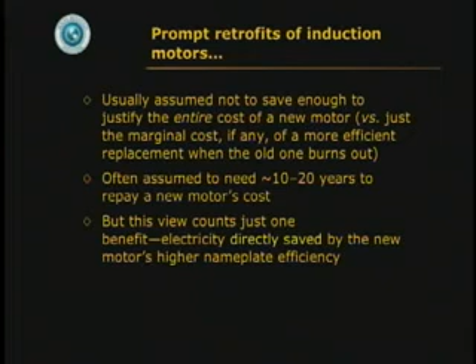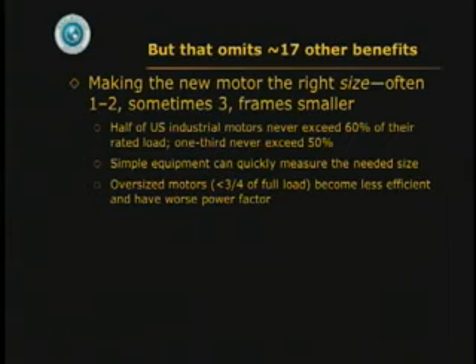It turns out that half of our industrial motors never get above 60% of their rated load. A third of them never exceed 50% of their rated load. In other words, they're way oversized because the size was marked up by several layers of bureaucracy. Who got fired for making a motor too big? But maybe you can get fired for making it too small. And it's easy to measure the size you actually need. PG&E invented that procedure. So you can often make the new motor a frame or two smaller, sometimes 3. Well, it turns out that when motors are oversized, they become less efficient and they have definitely worse power factor, and they also run faster, which wastes even more energy, say with a fan or pump flow that you don't really need. So when you put in a new motor the right size, not only can you make it more efficient, but it will save more and cost less than you would expect from comparing efficiency nameplate ratings that don't count the size effects.